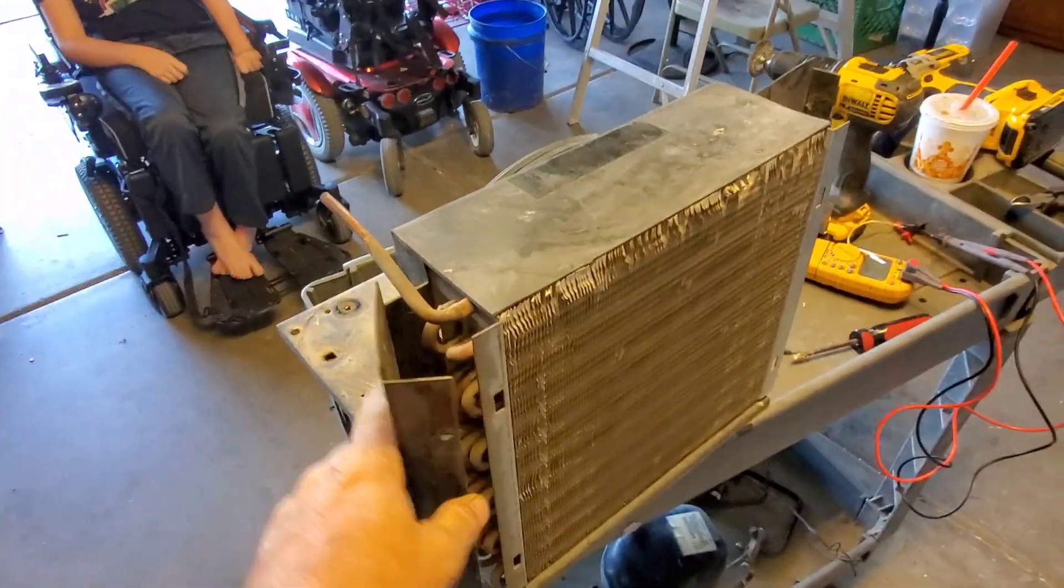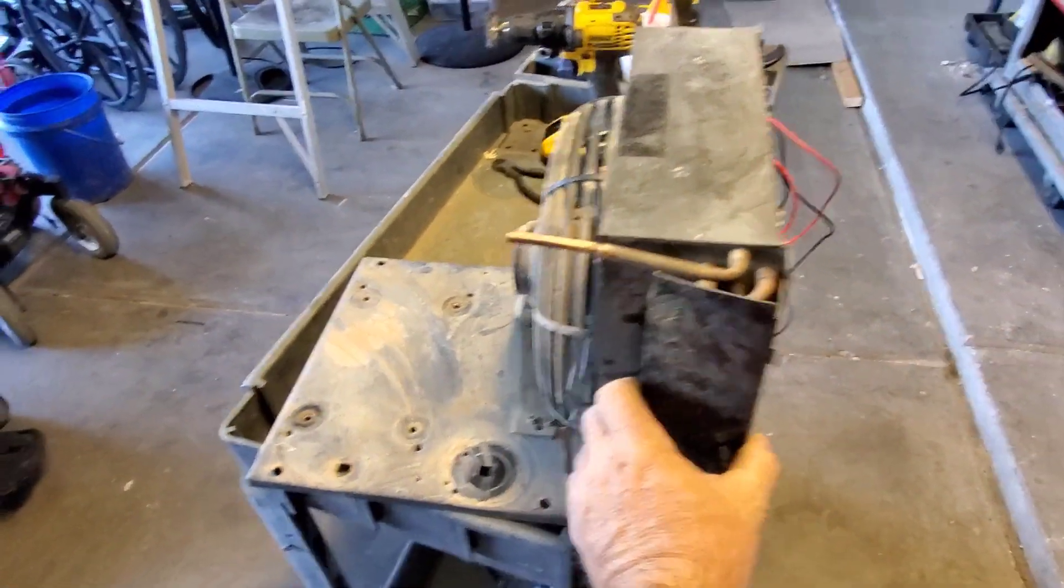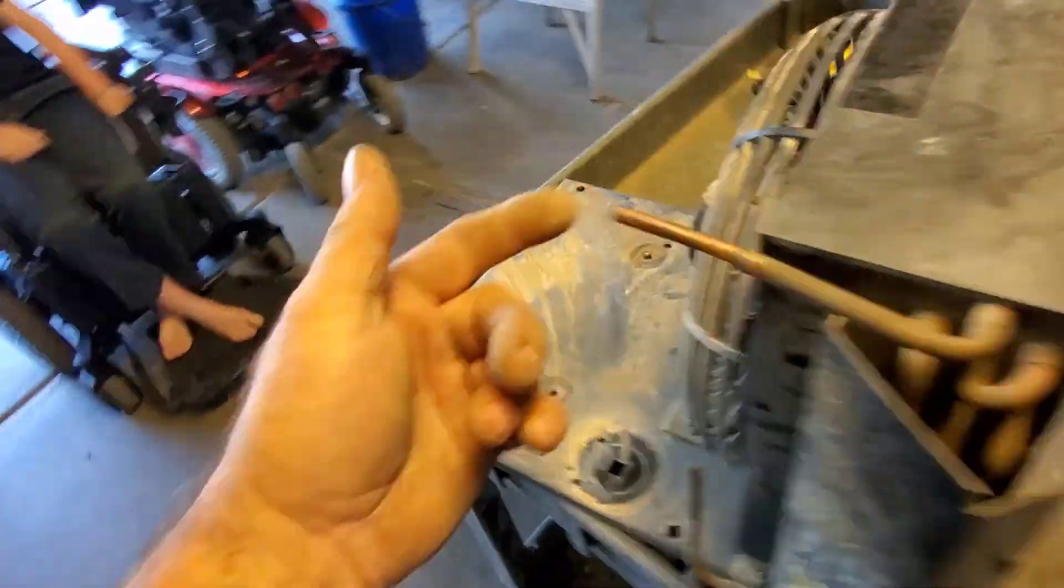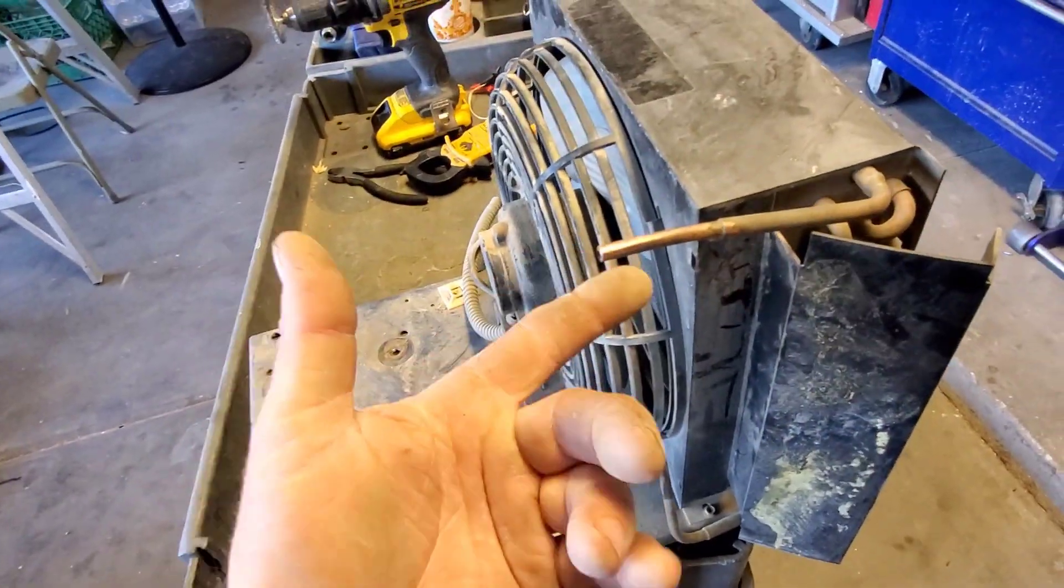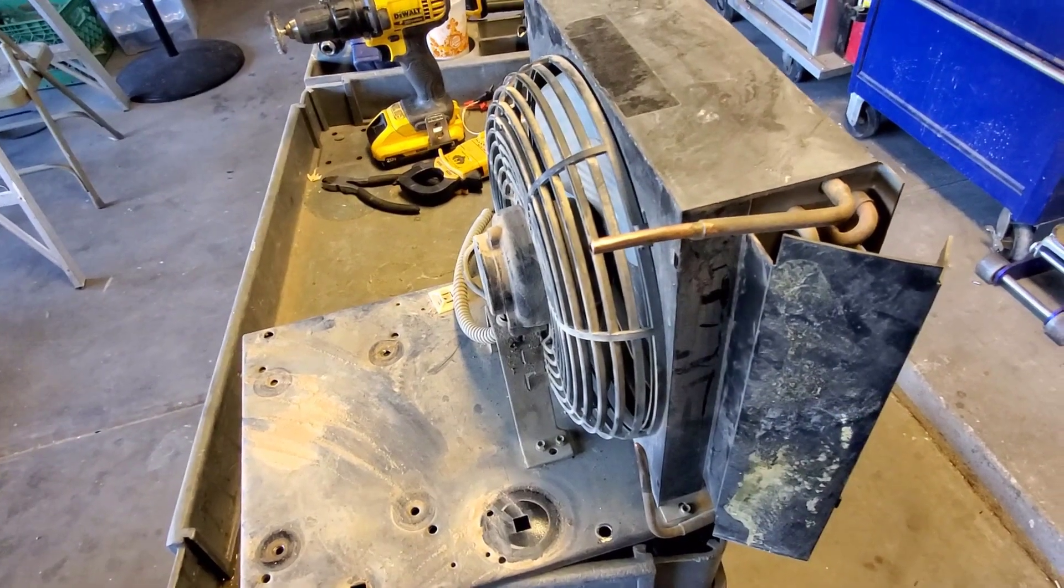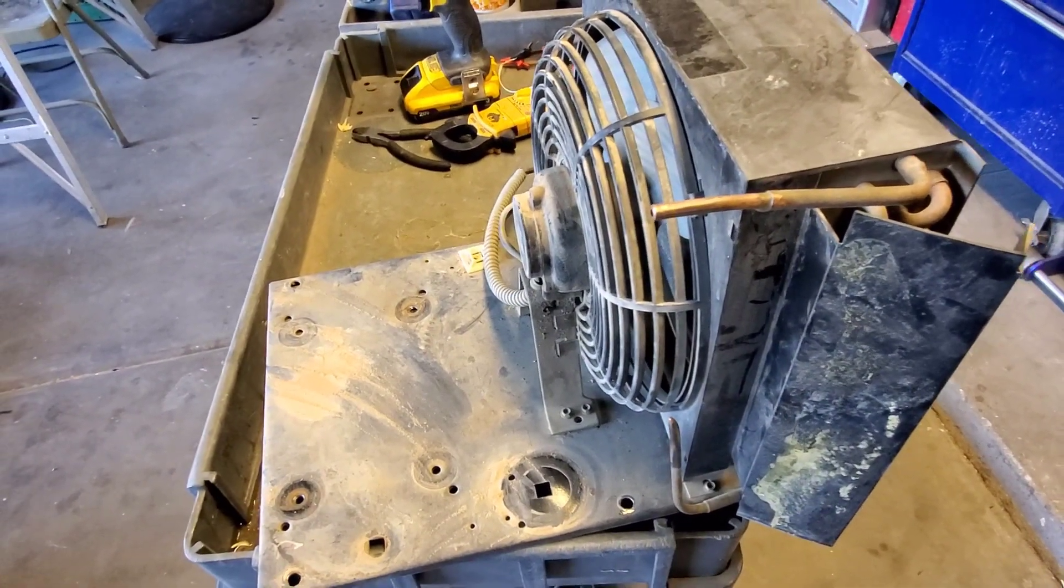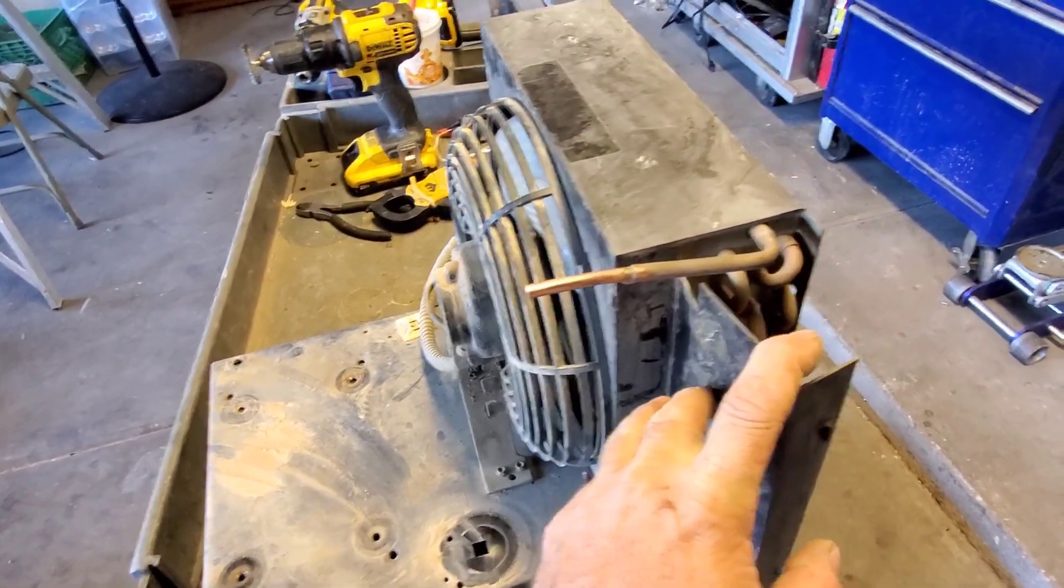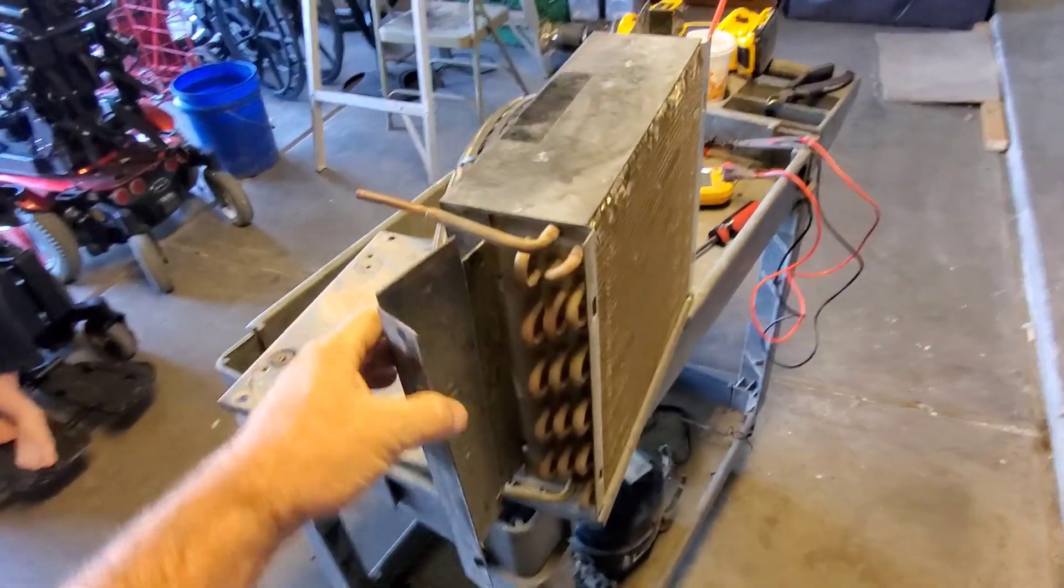Then I came out here cutting the pipes off and I'm like, wait a minute, it's only a quarter inch pipe. That seems a little small for suction even though it's gonna be one ton capacity, 12,000 BTUs.